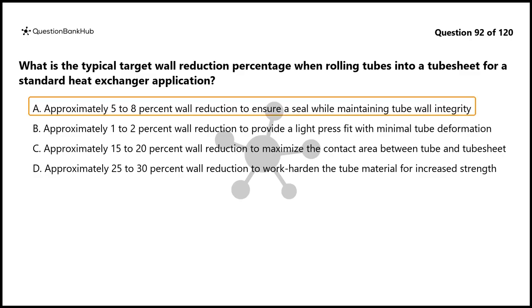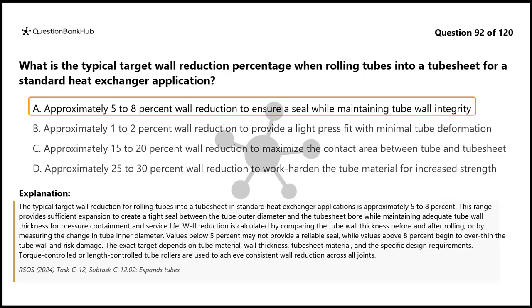The correct answer is A. The typical target wall reduction for rolling tubes into a tube sheet in standard heat exchanger applications is approximately 5 to 8%. This range provides sufficient expansion to create a tight seal between the tube outer diameter and the tube sheet bore while maintaining adequate tube wall thickness for pressure containment and service life.